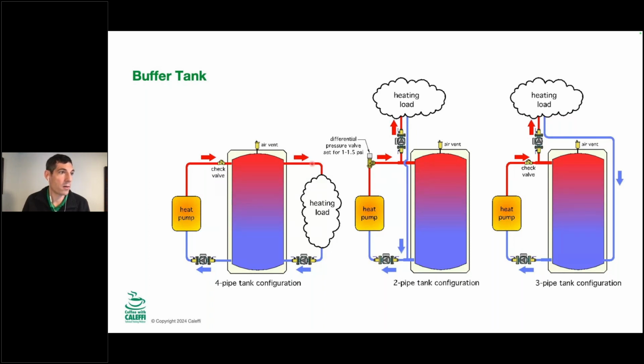We had this come up with a project I was involved with a long time ago where they had 180 degrees coming out of the boilers, but the indirect tank was piped over here. So they had an outdoor reset schedule for the building. So in the summer, they didn't need 180 degree Fahrenheit water to go out to the building. Unfortunately, they always needed 180 degrees to go to the indirect coil that came off here to heat water for the building. So because of that, they always had to have this buffer tank at 185 degrees to make sure that they got 180 degrees through that. And that was a very warm mechanical room because that buffer tank was huge, and you just had an enormous column of water sitting at 180 degrees all the way through the summer. So that made for a toasty mechanical room.